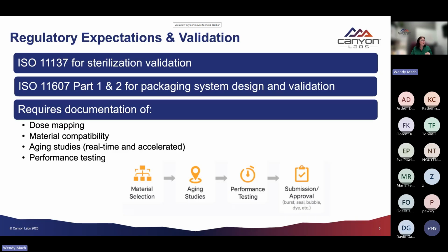11607 captures those real life aging studies and performance testing, and part of that is making sure that you have the data, which is presented using dye or bubble tests and peel strength. Additionally, you can take a look at microbial barrier testing, a comparison between before accelerated aging and after accelerated aging, to demonstrate that there's no degradation in those material barrier properties is an included data point. And then finally, visual inspection criteria, making sure that as time evolves, we're not seeing yellowing or warping. It's important to recognize that validation isn't just about passing tests, it's about proving that the long-term packaging performance under real-world conditions is acceptable and documented.